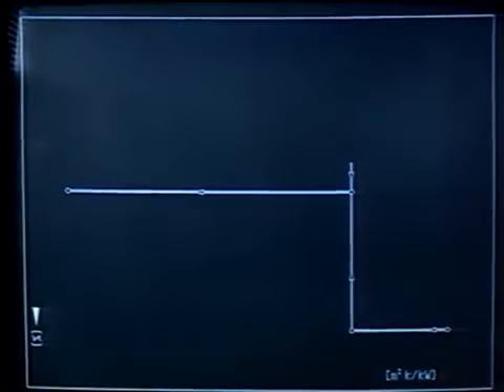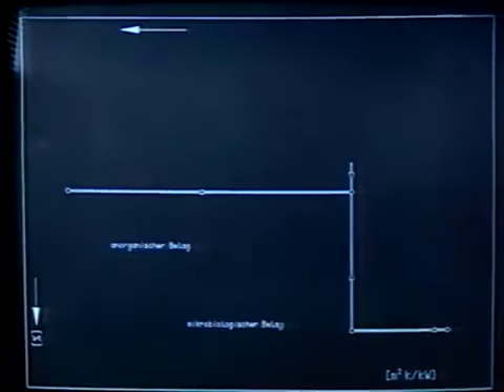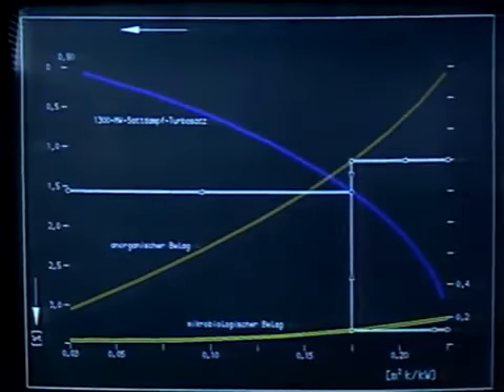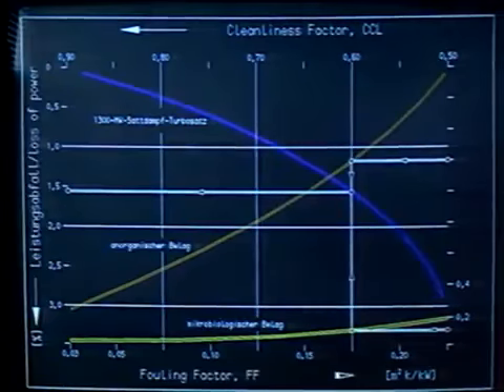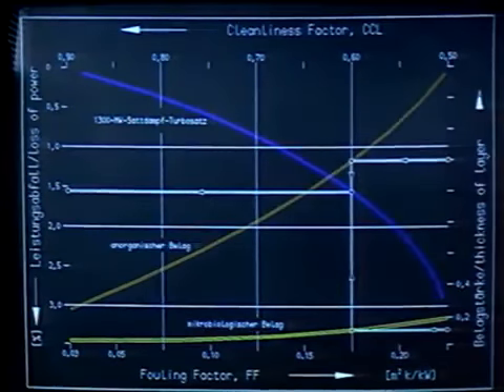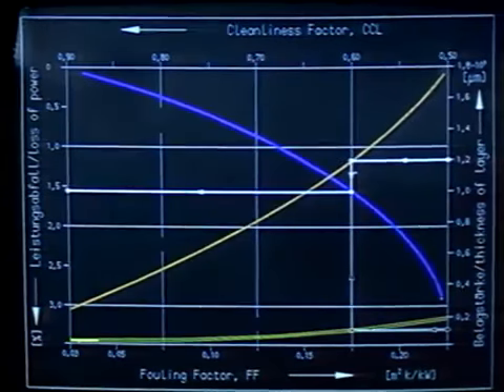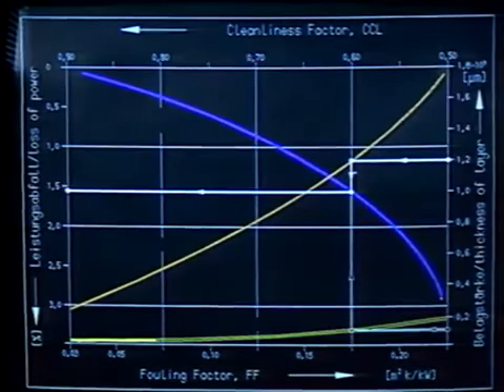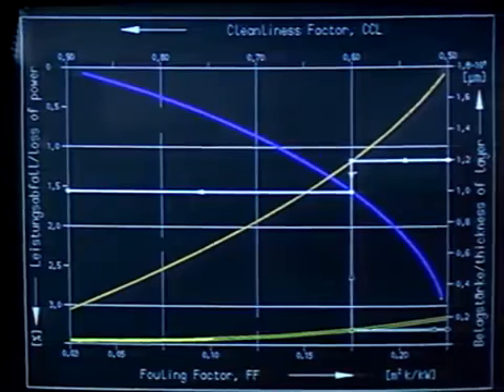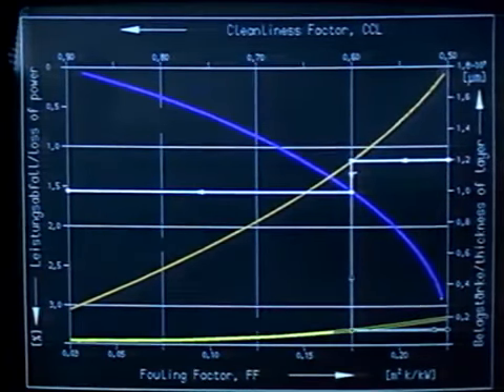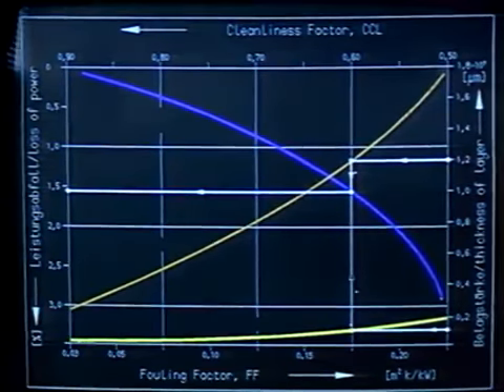In the condenser of a 1300 megawatt power station, a 0.12 millimeter thick layer of calcium carbonate reduces output by 1.6%. Bioslime, only 0.026 millimeter thick, will cause a similar output loss in a titanium tube condenser of a power station cooled with seawater. Though almost invisible to the human eye, these unwanted deposits still trigger substantial power losses.